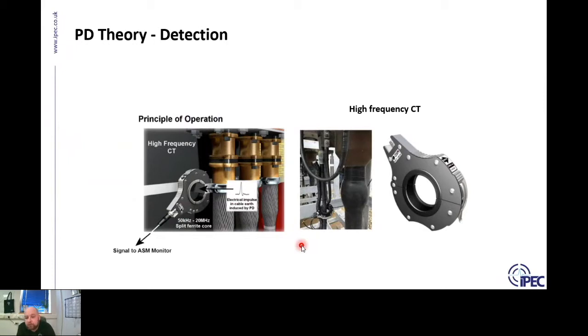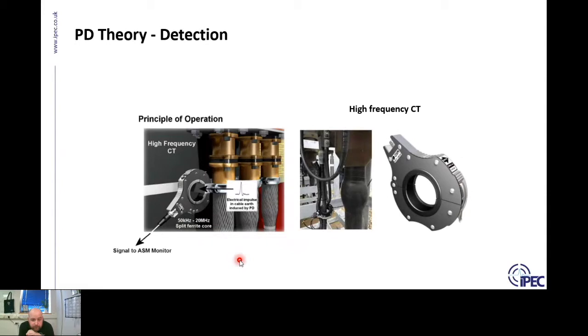For underground cables we use high frequency current transformers — HFCTs. They're pretty industry standard for detection of PD in underground cables. Each HFCT is different and must be considered individually. Recently IPEC have upgraded our HFCTs to a much wider bandwidth; our HFCT response is now up to around 70 megahertz, making it also quite effective at detecting switchgear PD at the same time as cable PD.